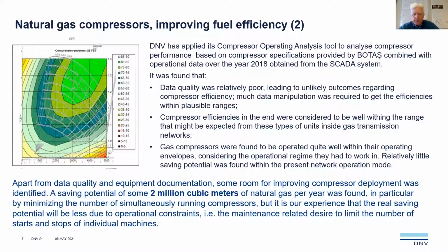Studying the compressor operations at the various compressor stations revealed that the quality of the SCADA data and equipment specifications to work with was rather poor. But after some data repairs, we found that the gas compressors are working well within efficiency ranges that may be expected. In total, a savings potential of some 2 million cubic meter of natural gas was found by allowing the compressors to run at more efficient working points, but it has to be noticed that such savings in reality cannot be achieved in total due to operational restraints like the strong desire to minimize the number of starts and stops to prevent thermal shocks harming the compressor units too much.